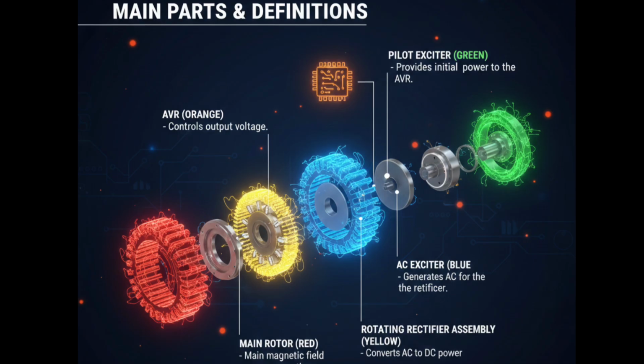Observe the diode bridges in the animation and the glowing yellow arrows showing DC flow. Main rotor creates magnetic flux. Notice how the flux lines in red extend into the stator windings. Pilot exciter, if included, provides a reference voltage for accurate AVR operation. AVR automatically adjusts field excitation to maintain output voltage.